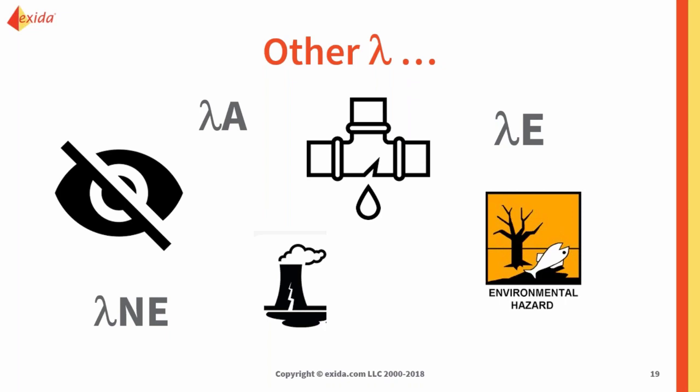These other failure rates, most of the time they're not going to be on the back of the certificate. There's just so much information you can cram onto a little area. However, these failures will all show up in a FMEDA report. It'll list all the relevant failures, including any no effect failures. So if you want to know more information, go back to the manufacturers and ask for the FMEDA reports and ask for the other failures. There's so many times when we have people only care about that dangerous undetected failure rate, and we try to let them know that there are many other things to be aware of. But a lot of people just want one number and done.